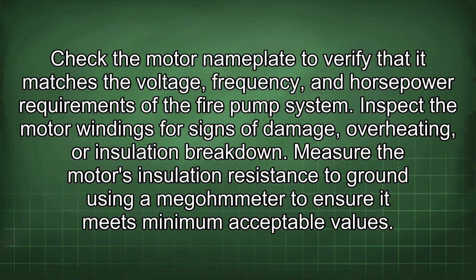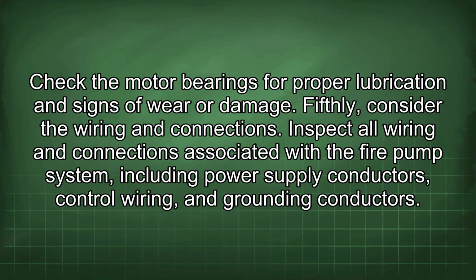Check the motor nameplate to verify that it matches the voltage, frequency, and horsepower requirements of the fire pump system. Inspect the motor windings for signs of damage, overheating, or insulation breakdown. Measure the motor's insulation resistance to ground using a megohmmeter to ensure it meets minimum acceptable values. Check the motor bearings for proper lubrication and signs of wear or damage.